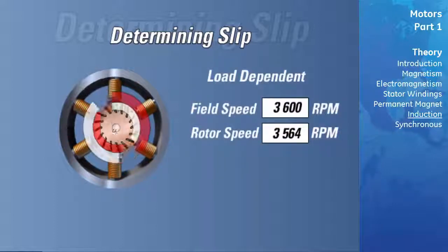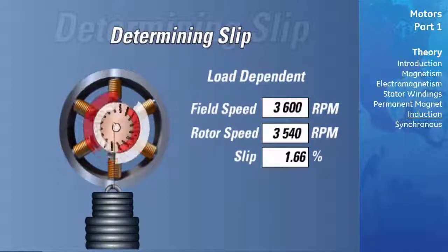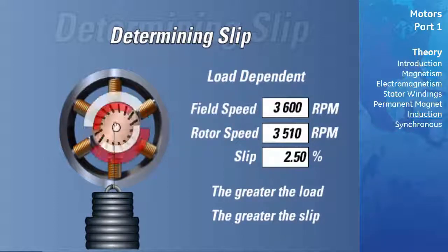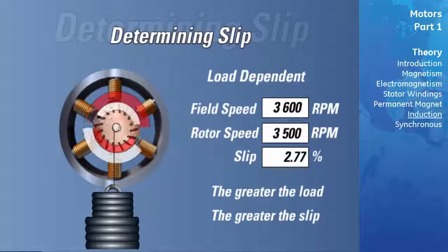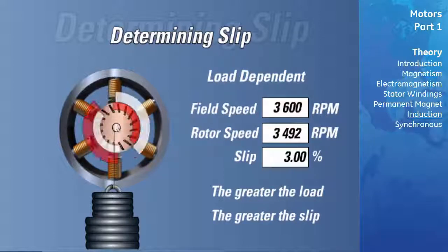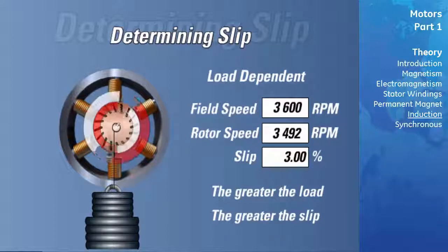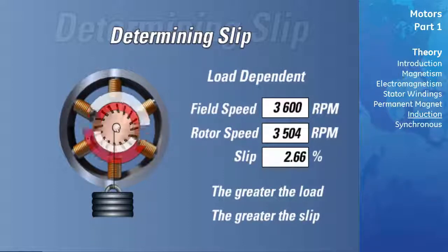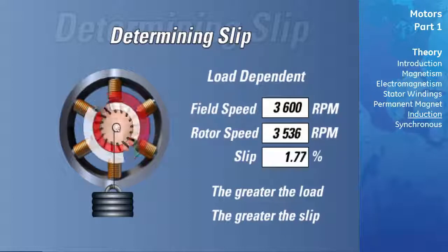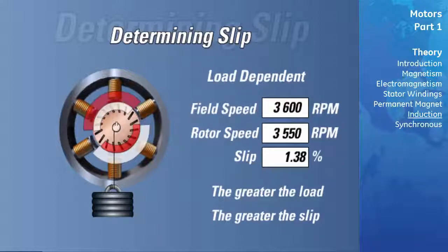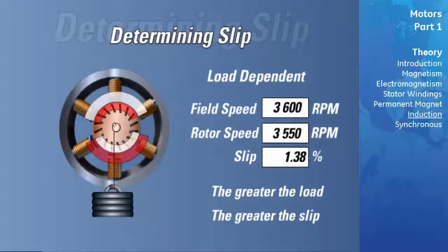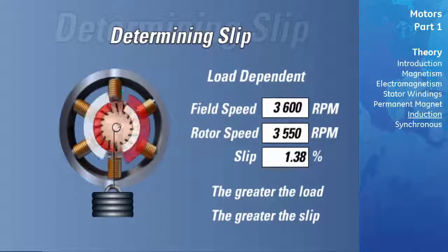Slip is load dependent. For example, if there is an increase in load, the rotor will slow down relative to the stator's rotating field. As a result, the lines of flux in the stator's magnetic field will cut the rotor bars at a faster relative speed, inducing a larger voltage in the rotor bars, which in turn induces a larger circulating rotor current. This larger rotor current produces a stronger rotor field, which interacts with the stator field to produce a stronger torque to overcome the increase in load. If the load were to decrease, the rotor will speed up, the stator field cuts the rotor bars at a slower relative speed, inducing a smaller voltage and lower rotor current. This lower rotor current produces a smaller, weaker rotor field, which interacts with the stator field to produce a lower torque to overcome the decrease in load.